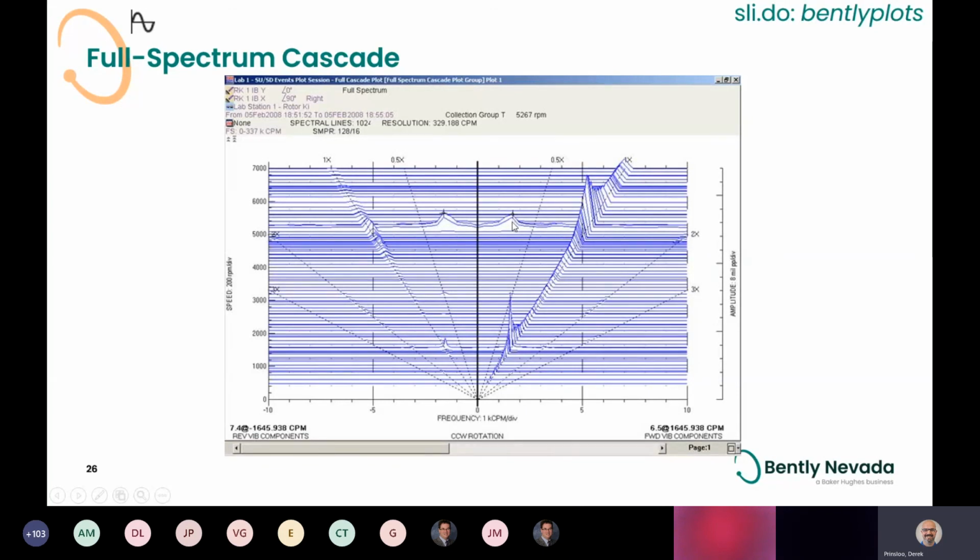And we can see now, by drawing a vertical correlation line through these, that those are the same frequency. This gives us a hint that there's probably some sort of structural resonance, and it's fairly low frequency down here. So maybe a structural resonance of something that got excited during that machine startup. This information could be used for stiffening structures and that.